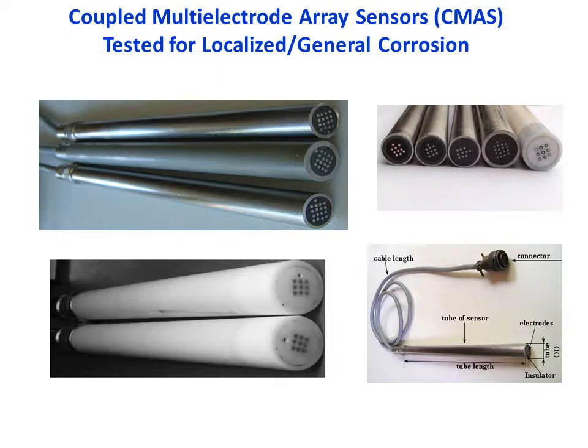To use the CMAS probe in multiple solutions, the probe can be sanded or ground down until the corrosion product or corroded electrodes have been removed, resulting in clean electrodes. The probe could then be placed in a new solution without measurements being affected by the probe's corrosion rate exposure history. Many clients refer to the CMAS probes as electronic coupons, due to the probe's capability of delivering real-time corrosion rate measurements. This is a key advantage of the CMAS technology, the ability to measure real-time corrosion rates and provide the client with constant feedback concerning the corrosion conditions in their process.